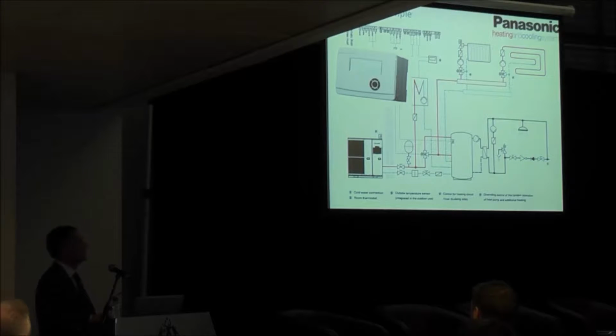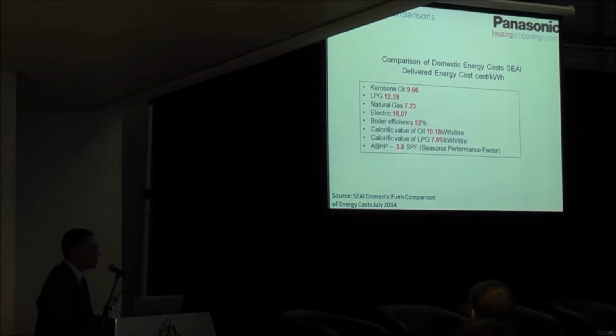Not finished. Just a couple more to go. That heat pump manager is not to scale, by the way. It's not huge. It's pretty small. So taking a look then at running costs and carbon emissions of air to water heat pumps against other forms of heating. These are the current domestic fuel cost comparisons on SEAI's website, and calorific values of oil and gas. And I've taken the air source heat pump, the air to water heat pump, having an SPF of 3.8. It's not the best, it's not the worst, I've just taken an average across the board.